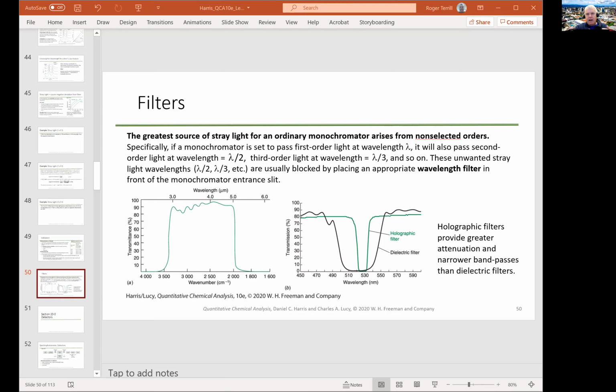If we let those photons into the detector, they will flood all of the pixels and we won't see our spectrum. The 785 nanometer light comes out like a Gaussian or a Lorentzian peak, and the tail will completely obscure our Raman spectrum unless we filter it out.